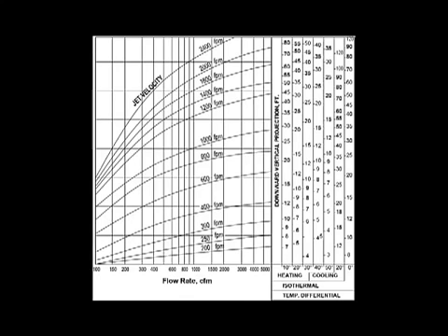The downward vertical projection diagram is one of the most useful diagrams in the Titus catalog because catalog data are always taken in isothermal conditions, basically 75-degree supply air in a 75-degree space, but diffusers are usually used in heating or cooling mode. Using this diagram and the diffuser performance, you can estimate the cooling and heating throw of a diffuser.